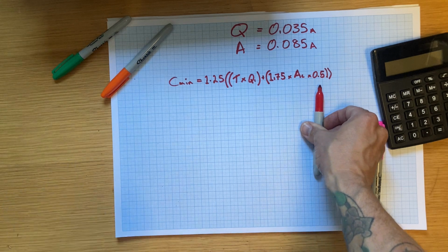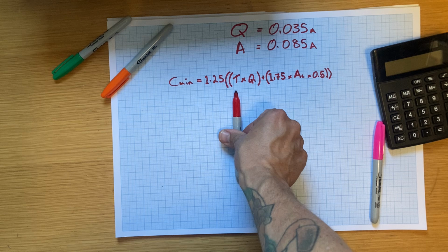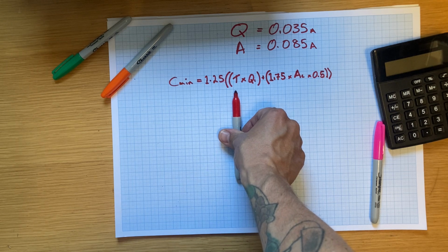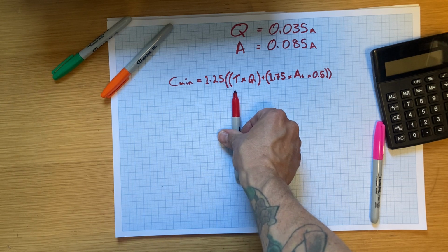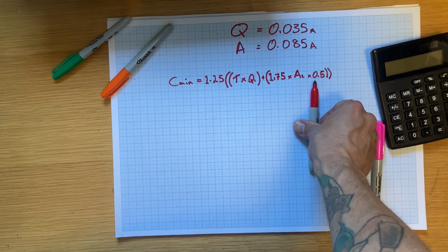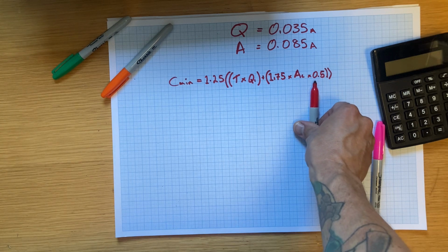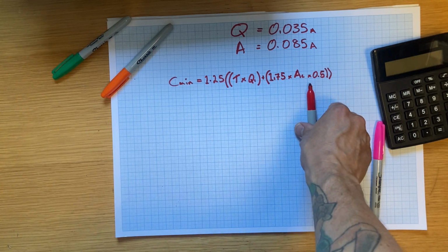The panel needs to be able to last the 24 hours of standby time, plus if in the last minute of that standby time, it's had no mains, the alarm goes off, it should be able to ring in full alarm for half an hour, which is obviously a bunch of load because it's the sounders and the visual alarm devices and all sorts, which is a bit more load.